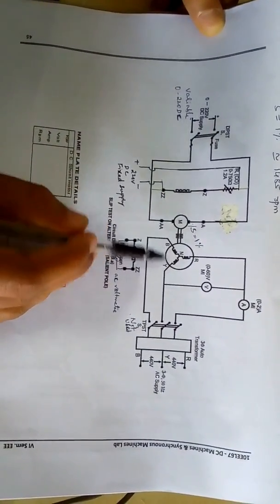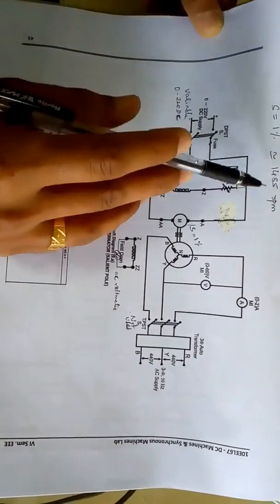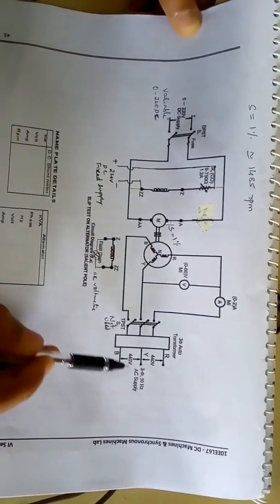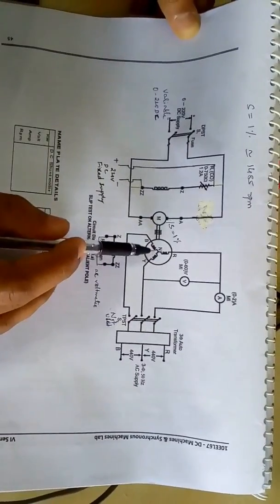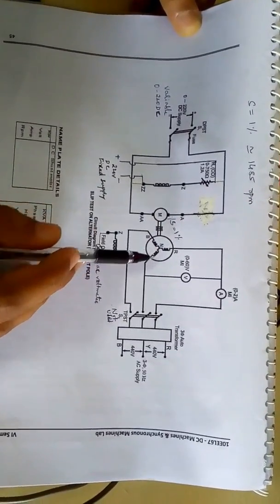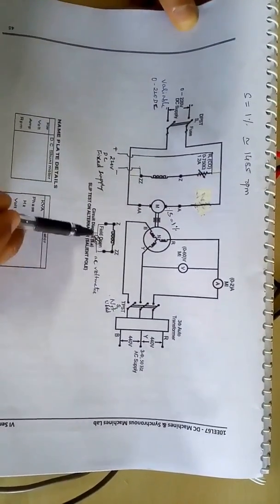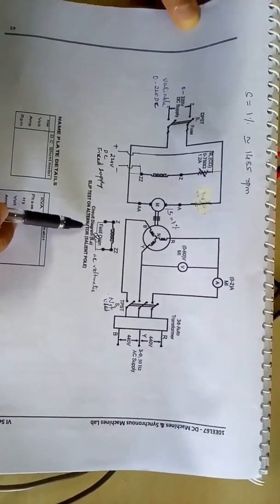the alternator at 1485 rpm, we should make sure that the three-phase supply given to the RYB (that is stator) should be in off position, that is S2 should be in off position, and field should be in open position.